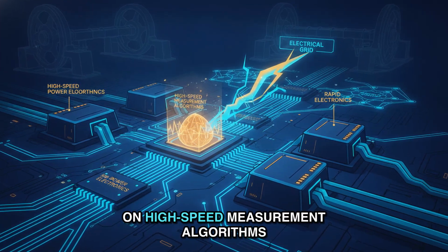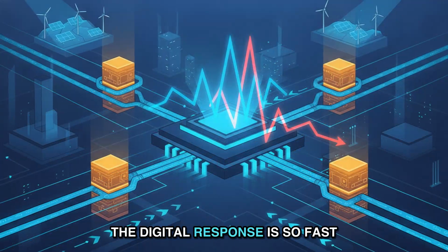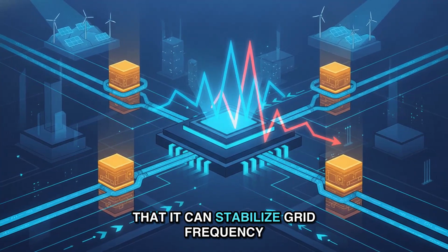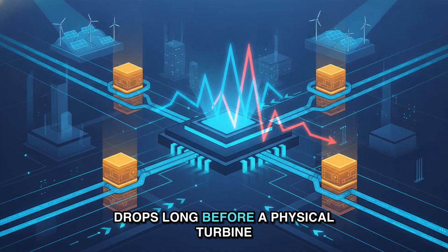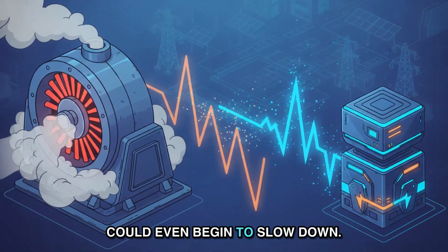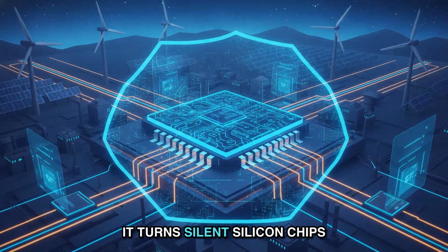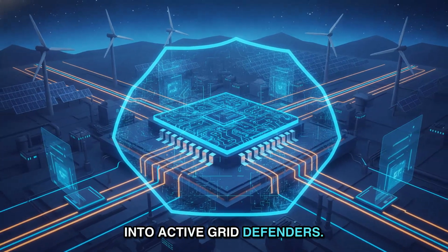Synthetic inertia does not rely on physical weight. It relies on high-speed measurement algorithms and rapid power electronics. The digital response is so fast that it can stabilize grid frequency drops long before a physical turbine could even begin to slow down. It turns silent silicon chips into active grid defenders.